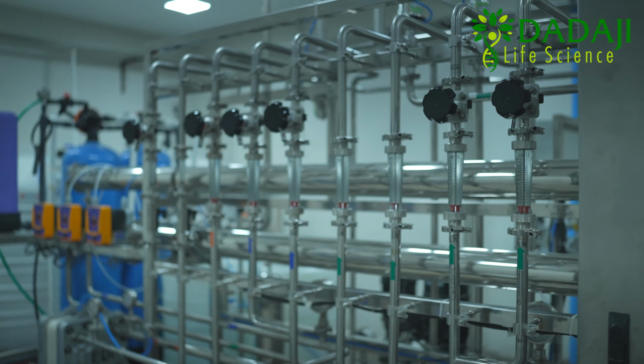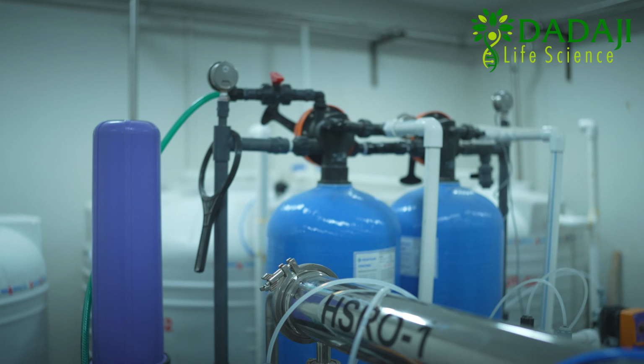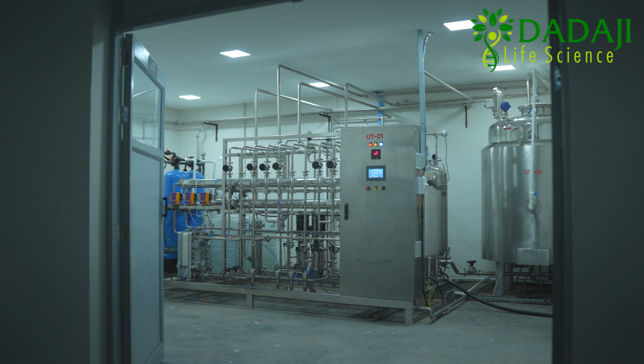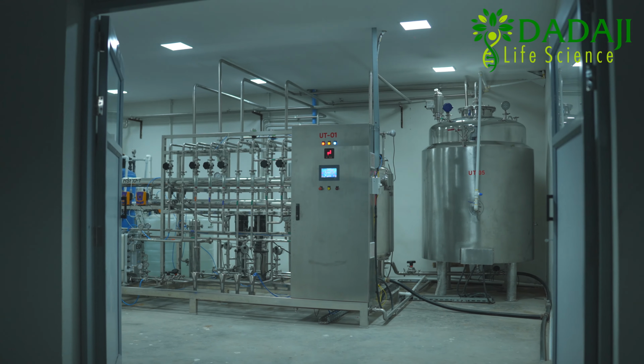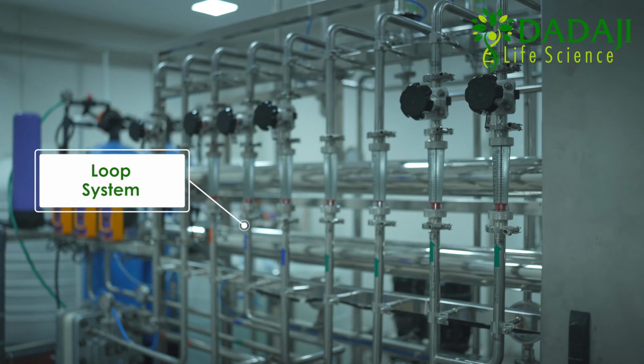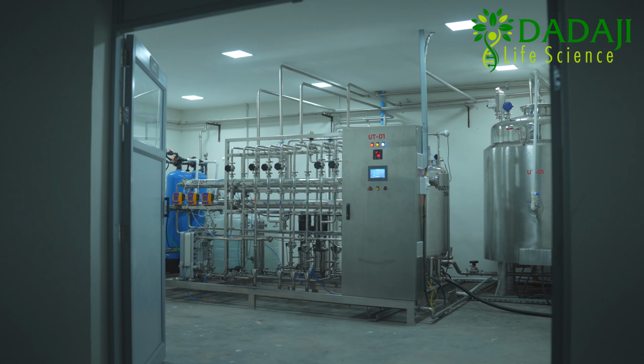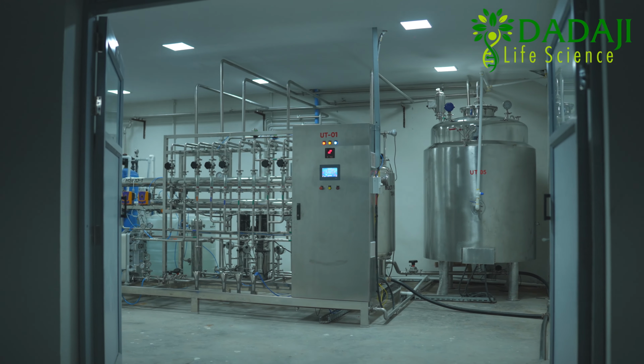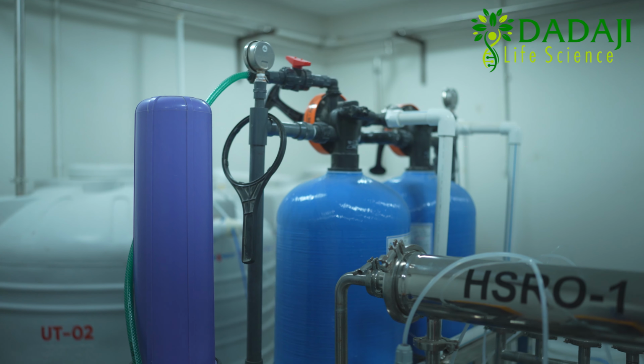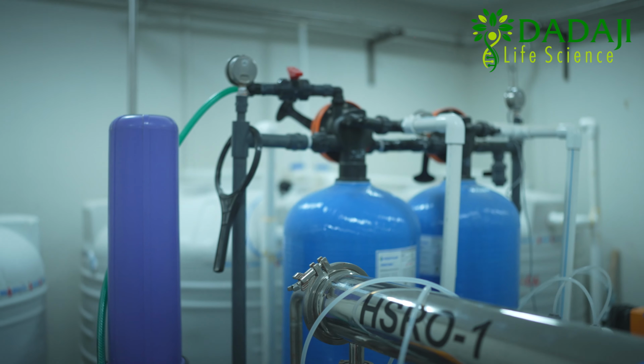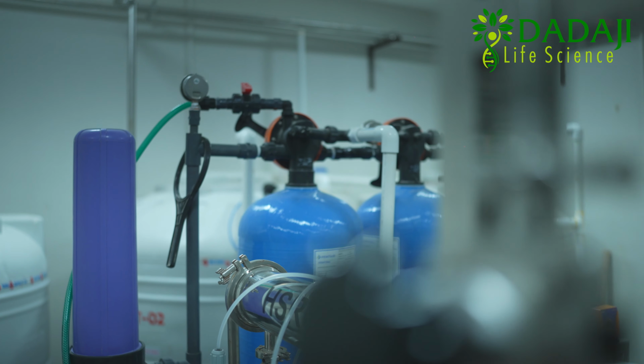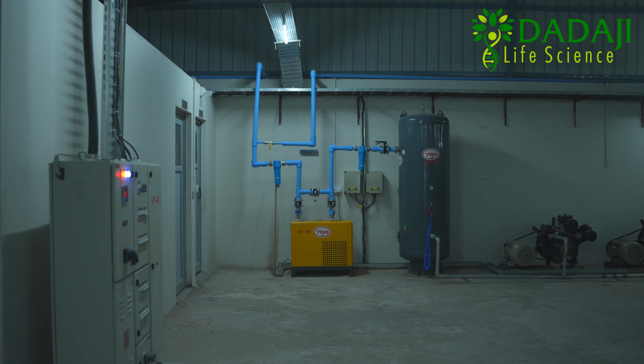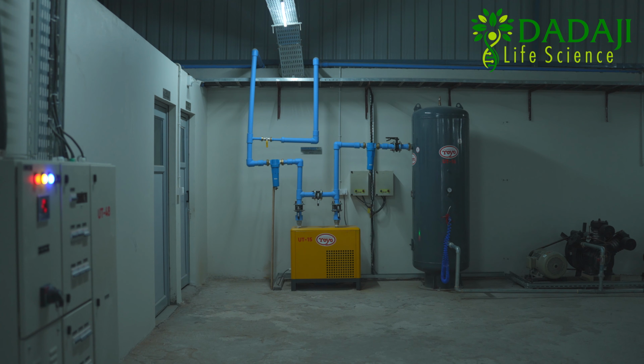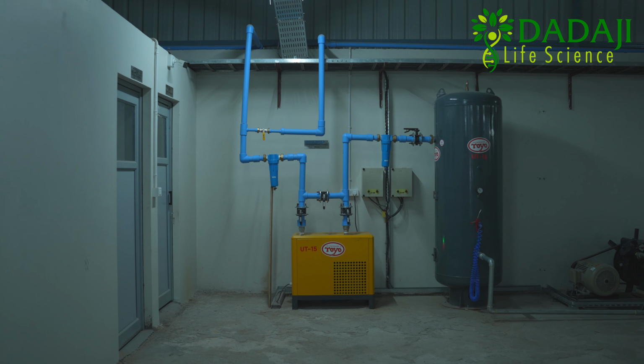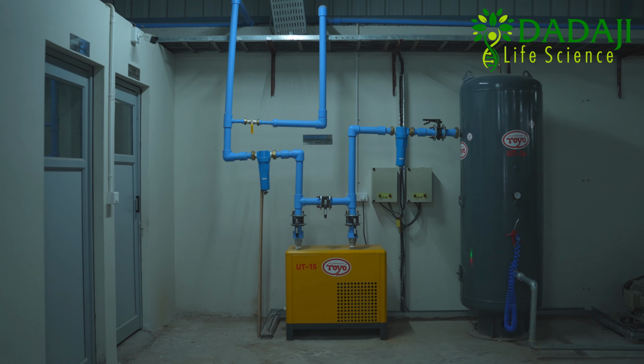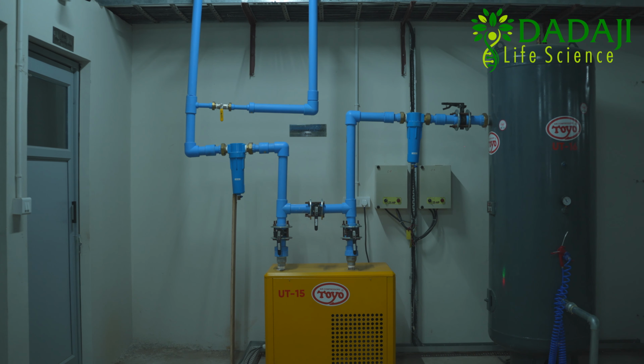Purified water used in the manufacturing of the product and cleaning of equipment parts and utensils is generated, stored, and distributed by an in-house purified water generation plant with a capacity of 500 liters per hour. This purified water is circulated by a loop system in various areas. These circulation loop systems are periodically cleaned by sanitizing procedures. For the supply of compressed air, we have 2 oil-free compressors with a storage capacity of 1000 liters. The compressed air is dried by using an air dryer before it is circulated to various processing areas of our plant.